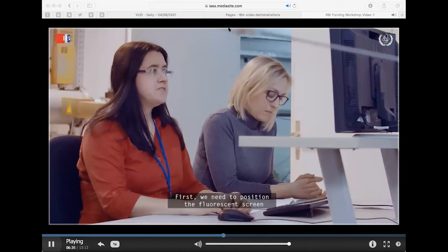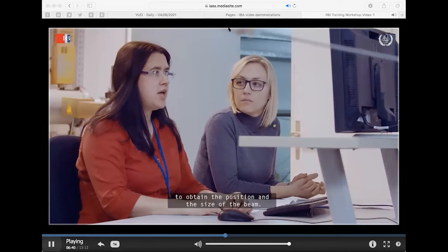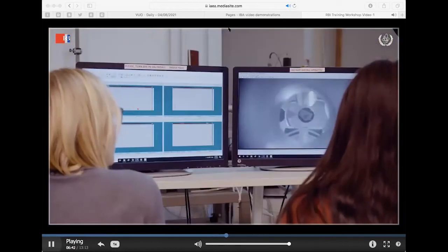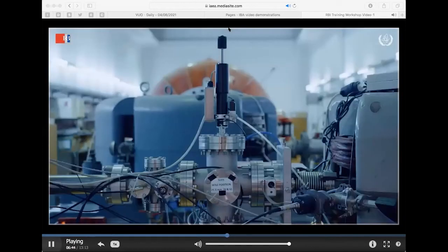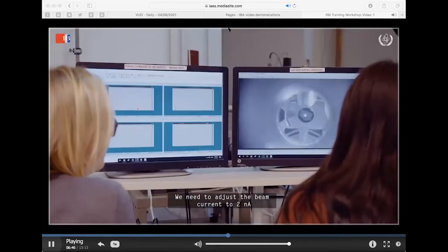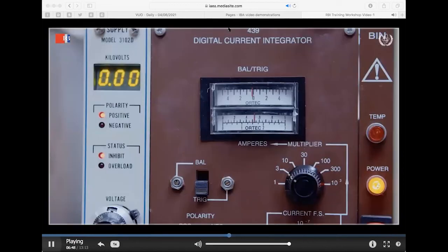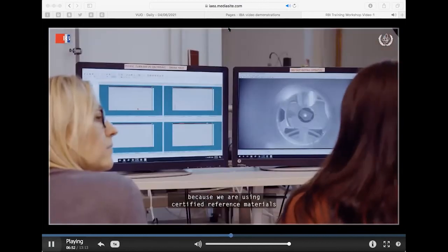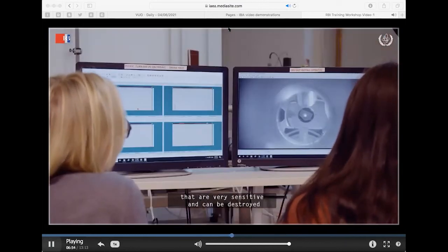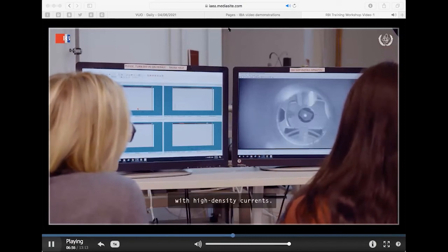Now we are passing the beam inside the chamber. First, we need to position the fluorescence screen to obtain the position and the size of the beam.